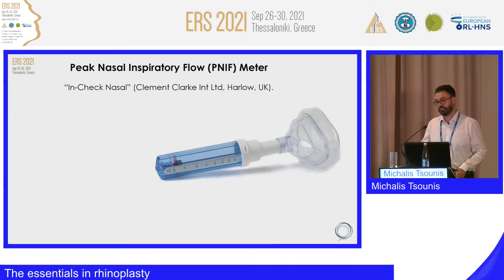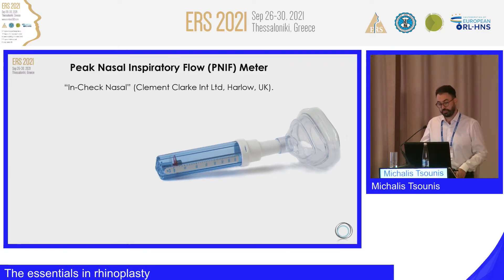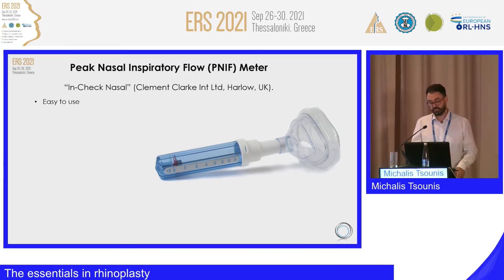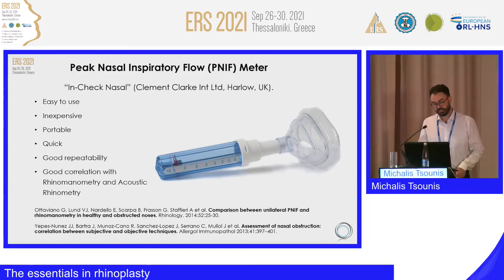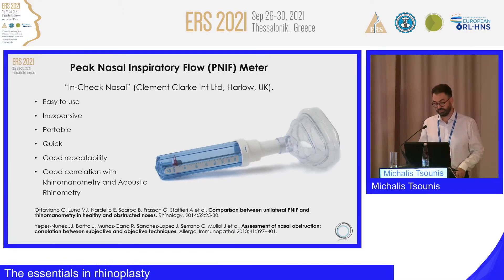Another device, less impressive but with important advantages, is the peak nasal inspiratory flow meter. It is very easy to use, cheap (about 35 pounds in the UK), portable, quick, and has good repeatability. According to recent studies, it has good correlation with rhinomanometry and acoustic rhinometry.